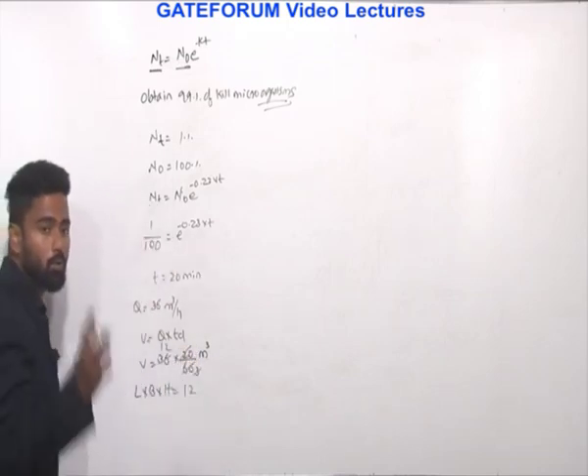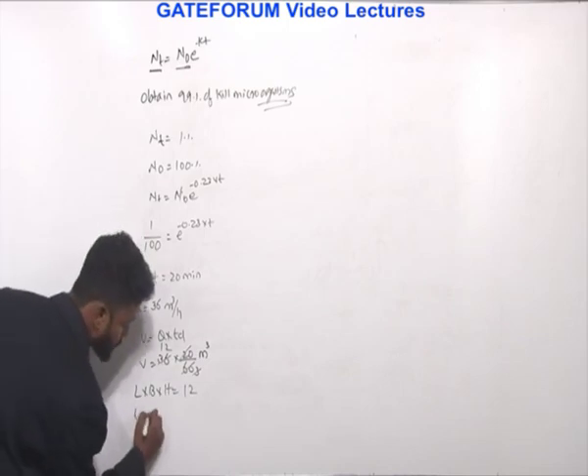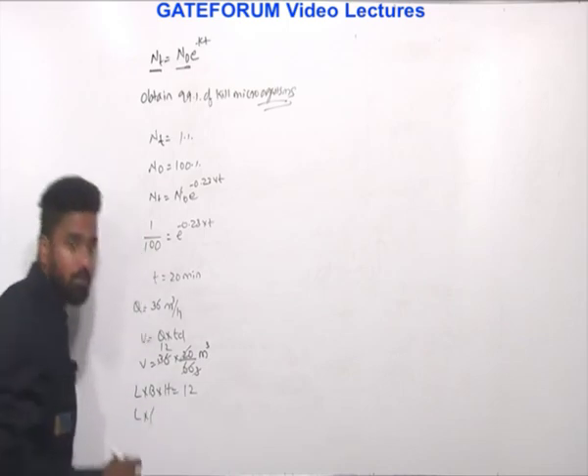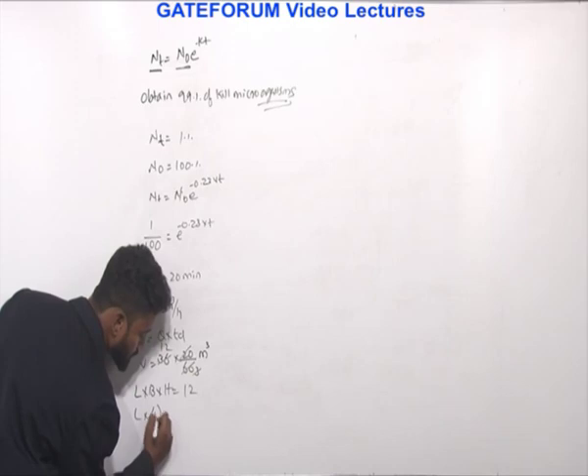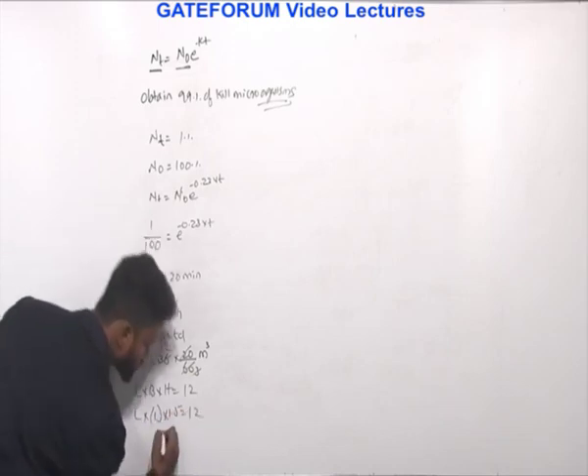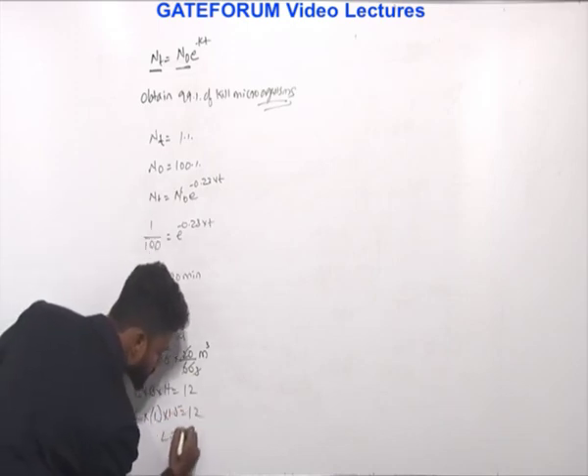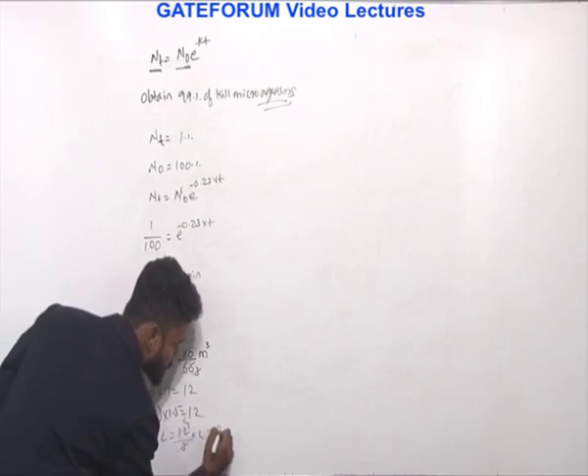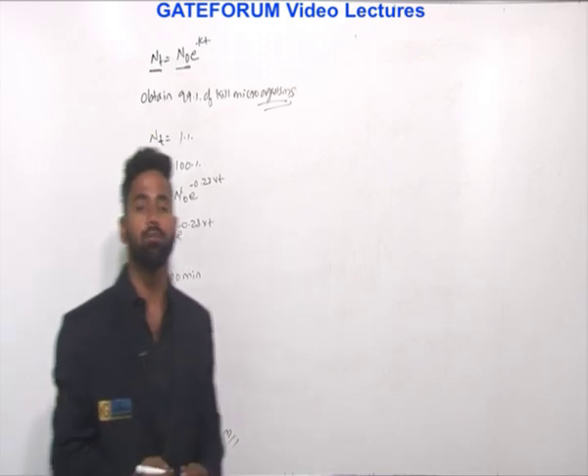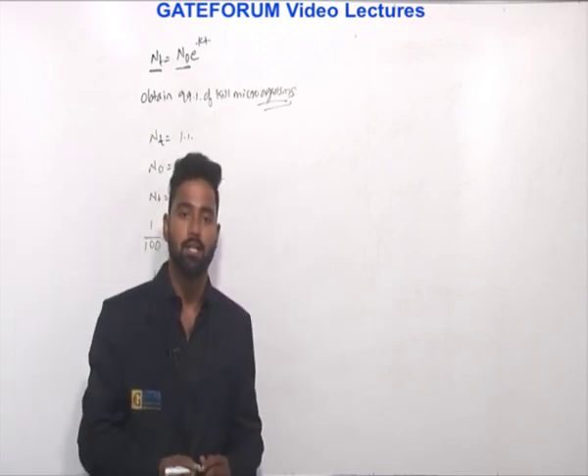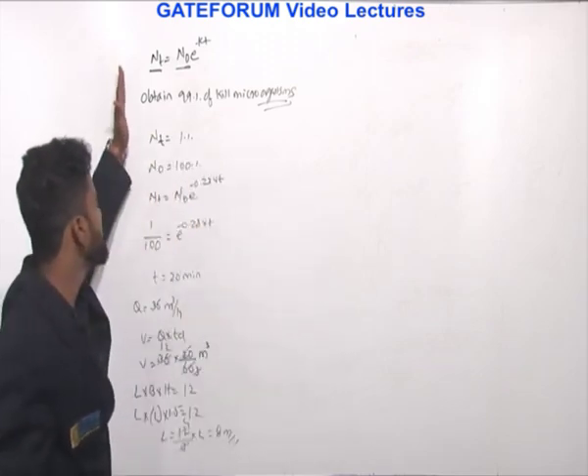Once we get the volume, L × B × H = 12 meter cube. The width is 1 meter and the depth is 1.5 meters. So L = 12 / (1.5 × 1) = 12 / 1.5 = 8 meters. This is how we calculate the length of the chlorination tank.